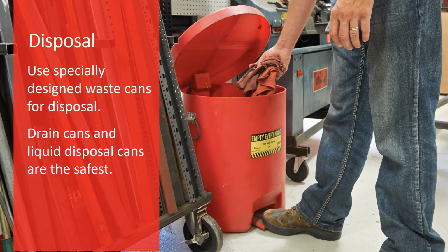Disposing of waste flammable liquids requires as much caution and handling as do any of the other stages. Oily, solvent-soaked rags can easily start a fire through spontaneous combustion. To prevent this, specially designated waste cans should always be used for temporary storage. These cans have spring-loaded lids and a raised bottom with vent holes to disperse heat. If these are not available in your trucks or vans, please return them to the shop as soon as possible to avoid any possible danger.